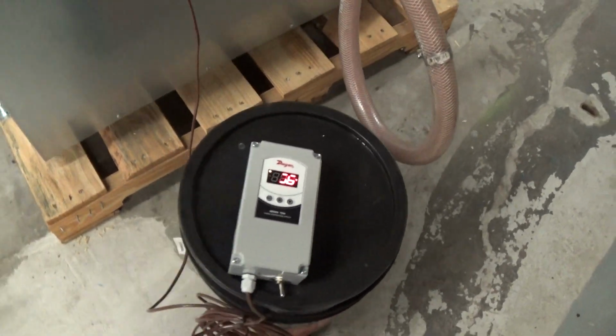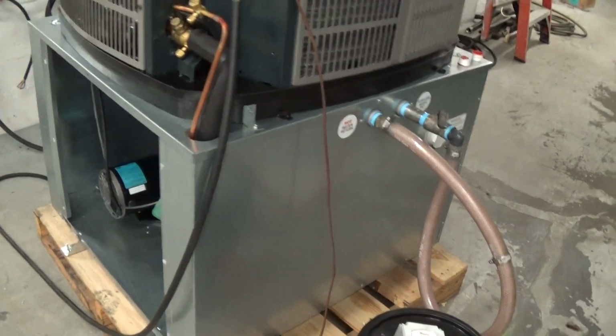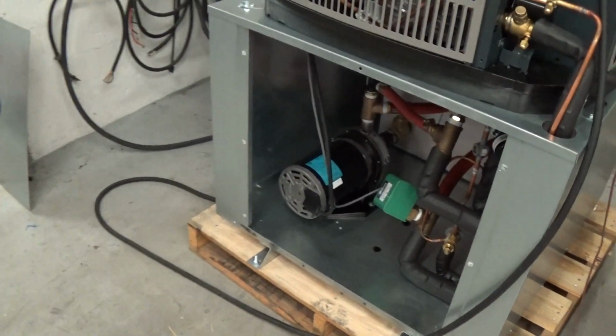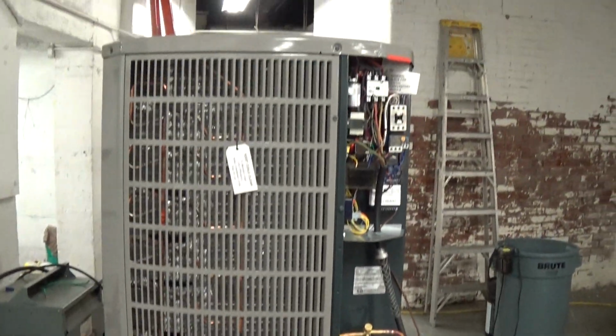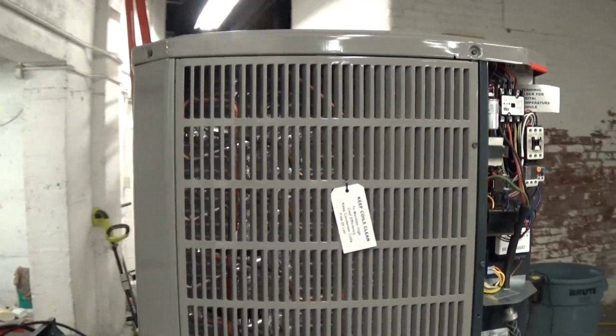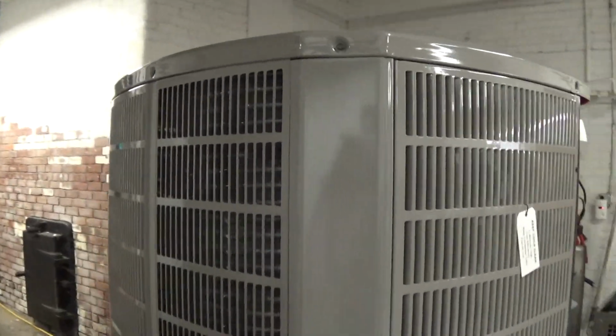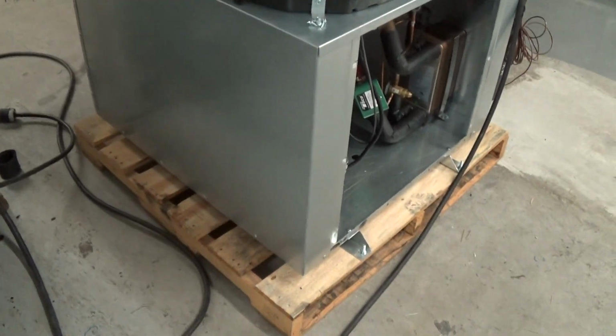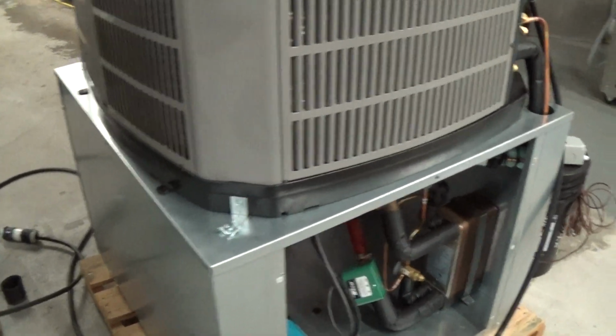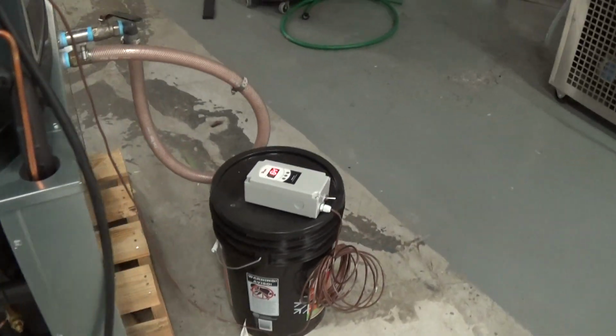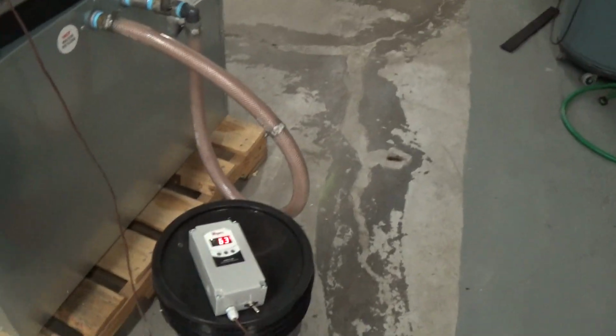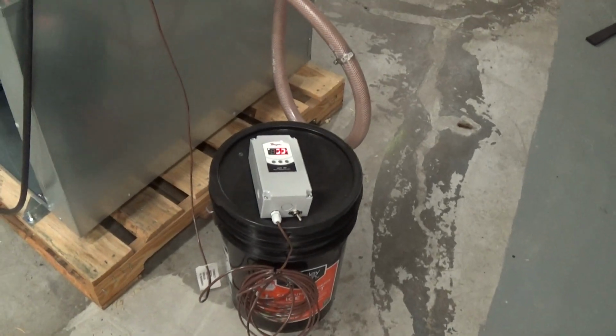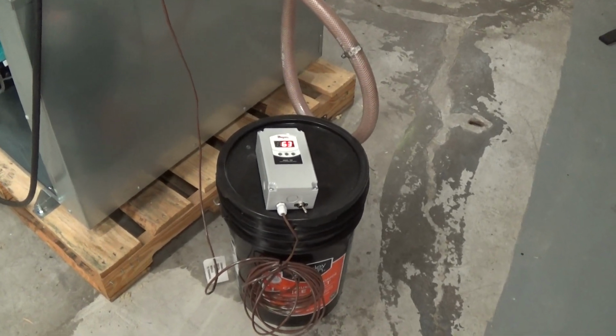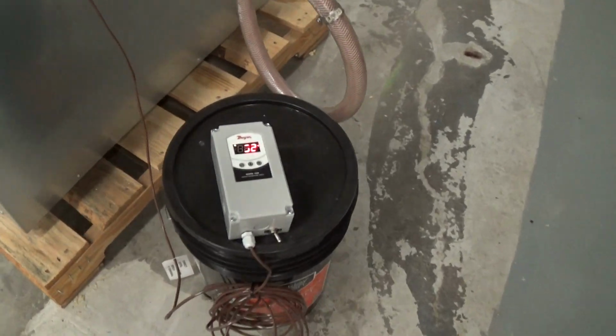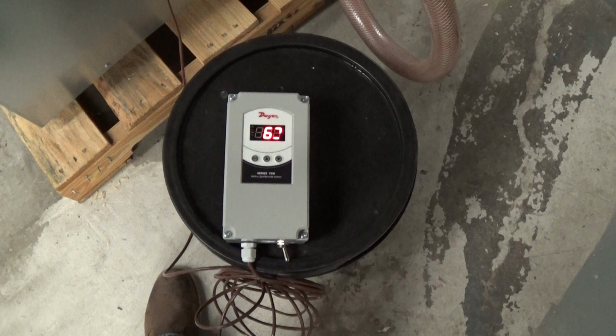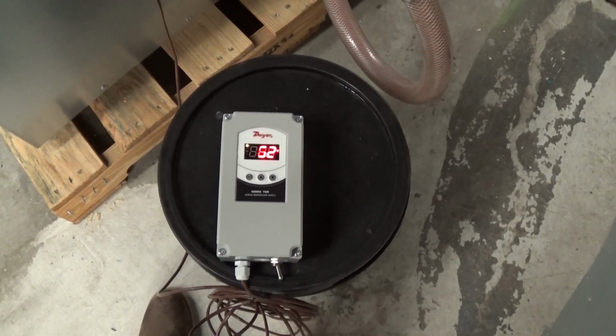And you want to run with a differential like that to prevent the frequent starts and stops of the compressor. If you have to tighten it up, call us. We'll give you instructions how to do it. But the tighter the differential, the more starts and stops you're going to put on your compressor. If you have a tight temperature tolerance application, there's other ways of achieving that through a separate heat exchanger and a separate small little controller to control a solenoid valve. So you can see the temperature's starting to drop right now. We'll have video number 2 when we get close to the set point.